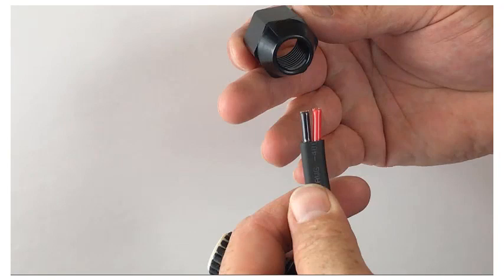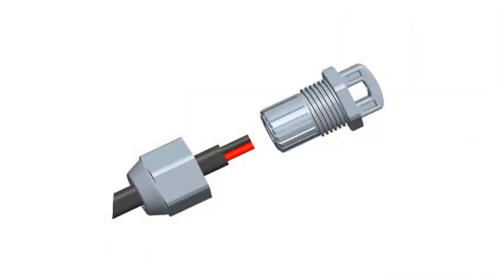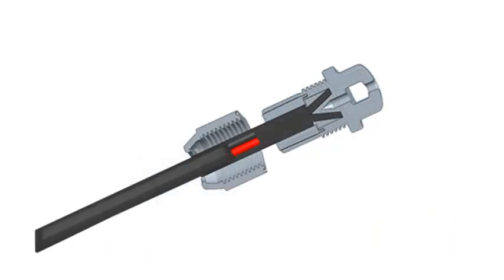Slide the hex nut onto the cable. Insert the cable into the Terminator body so that each of the two wires land on opposite sides of the internal separator. The grommet inside the Terminator body should remain in place.